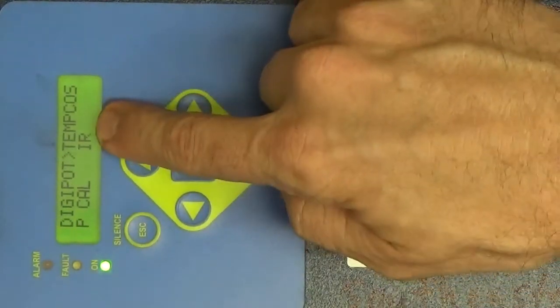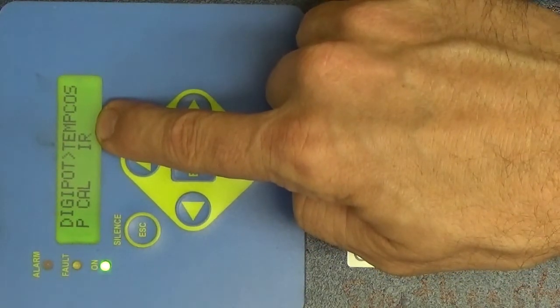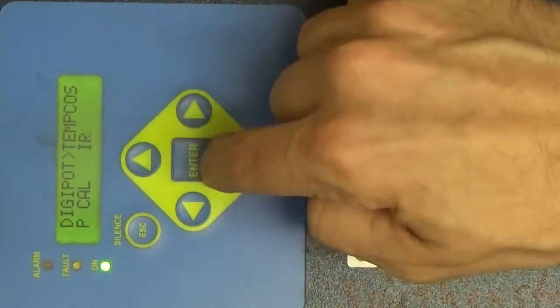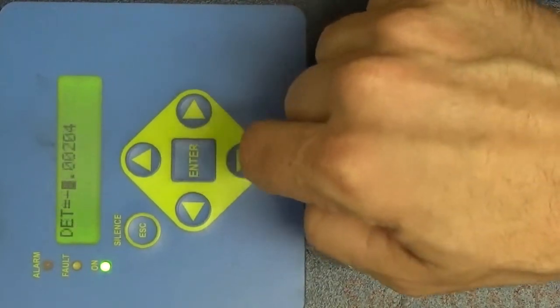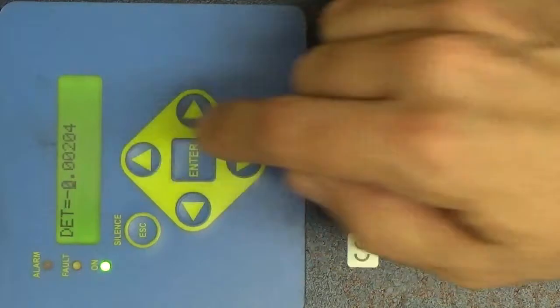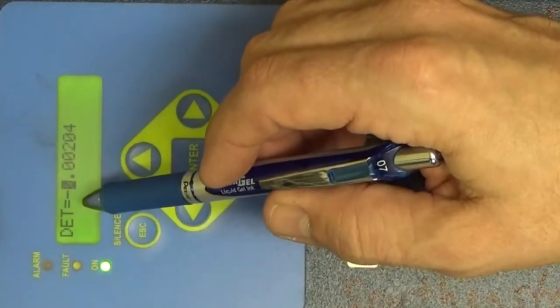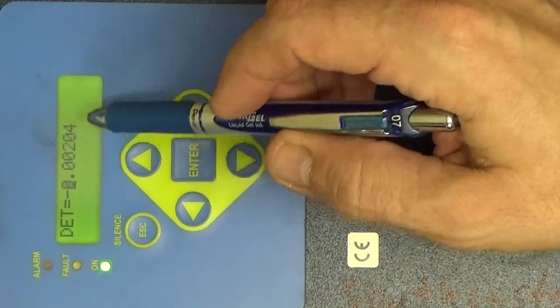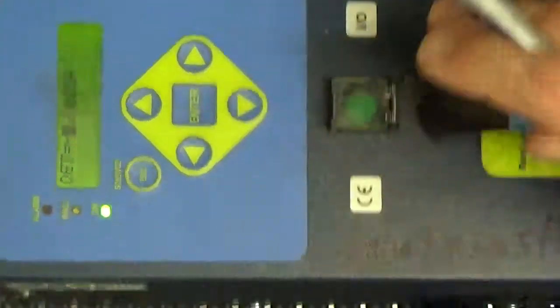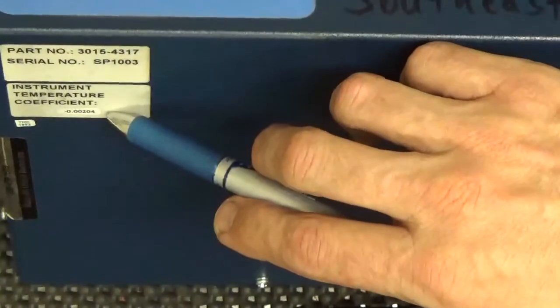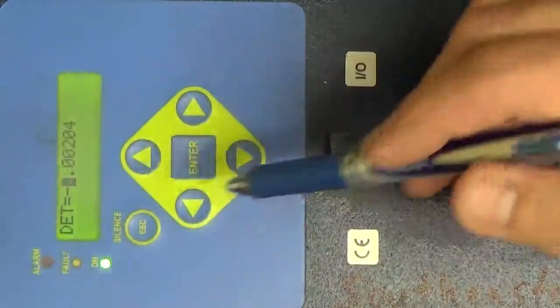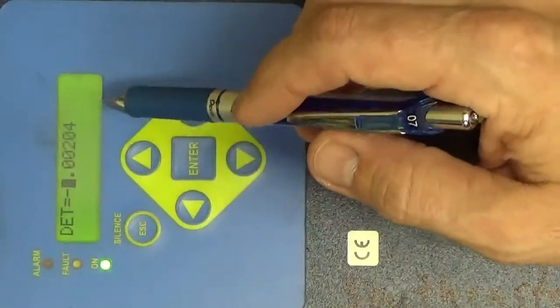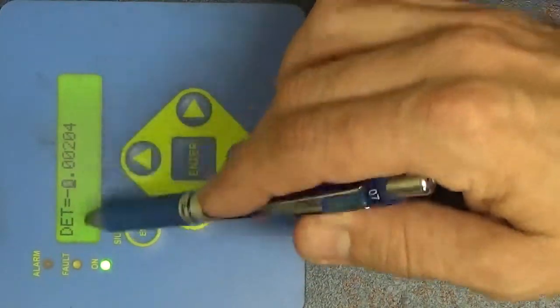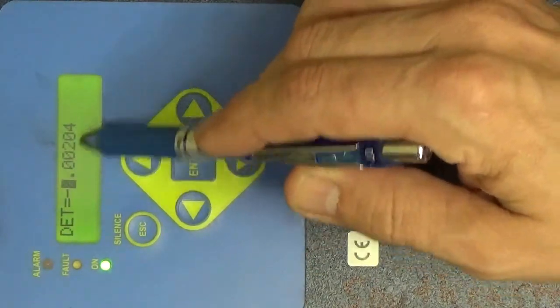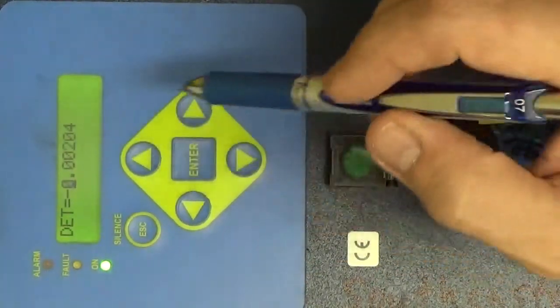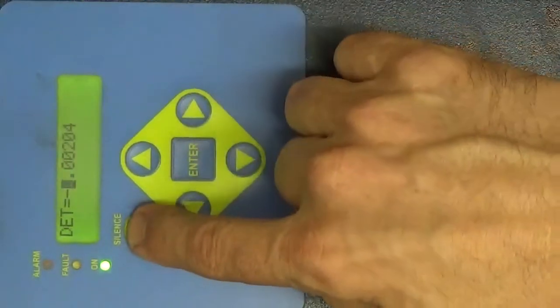Next thing we want to look at is something called temp, COS. This is our temperature coefficient. So again, move the menu there, hit enter, and confirm that the number that's recorded here, this is negative 00204, is the same as the number that's recorded on the side of the unit. If the internal battery has gone, what you'll probably see in here instead of an actual number is you'll just see all zeros, and that means that the internal lithium battery has failed. Again, hit escape to get back out.